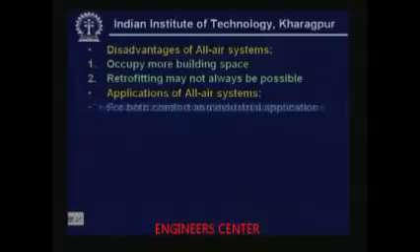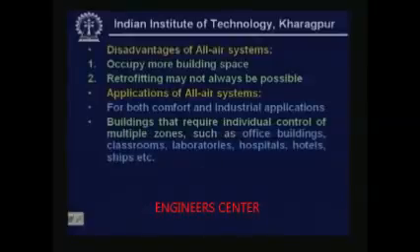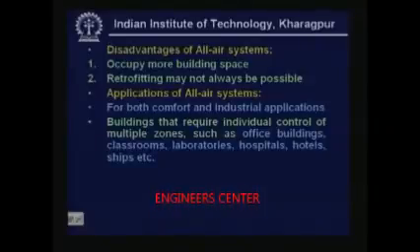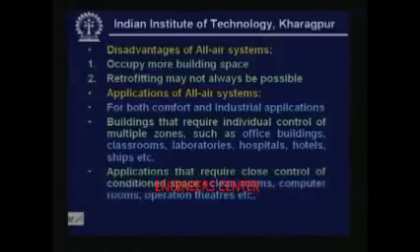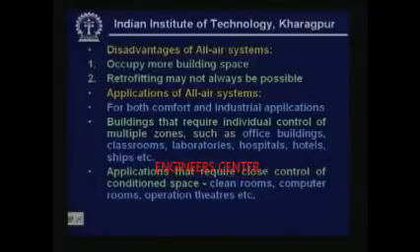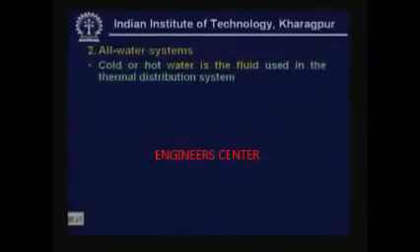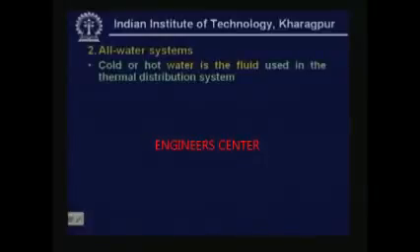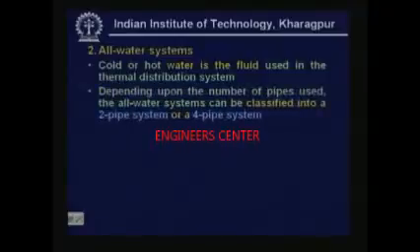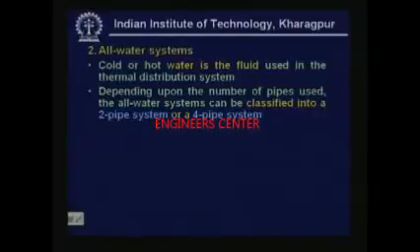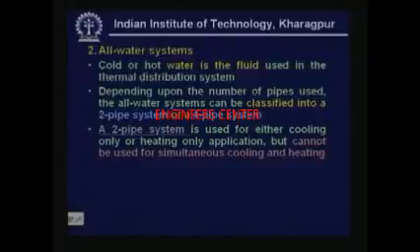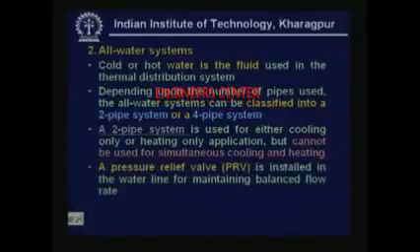What are the applications of all air systems? They are applied for both comfort as well as industrial air conditioning, and used in buildings that require individual control of multiple zones such as office buildings, classrooms, laboratories, and hospitals. They are also used in applications that require close control of the conditioned space, such as clean rooms, computer rooms, and operation theaters. Now let us look at all water systems. In all water systems, cold or hot water is the fluid used in the thermal distribution system. Depending on the number of pipes used, all water systems can be classified into a 2-pipe system or a 4-pipe system. A 2-pipe system is used for either cooling only or heating only, but cannot be used for simultaneous cooling and heating. A pressure relief valve (PRV) is installed in the water line for maintaining balanced flow rate.